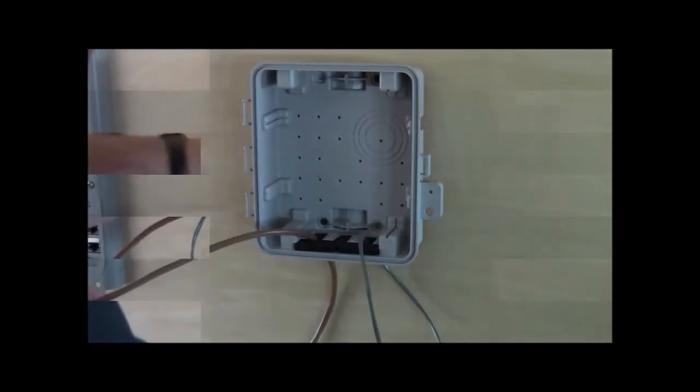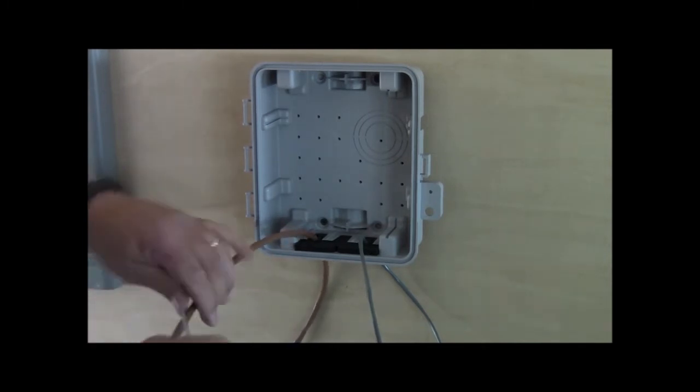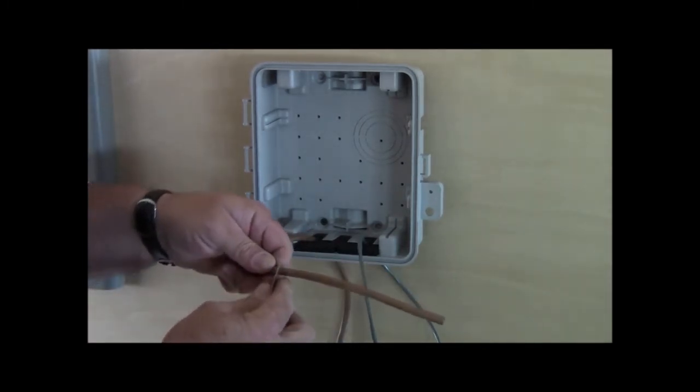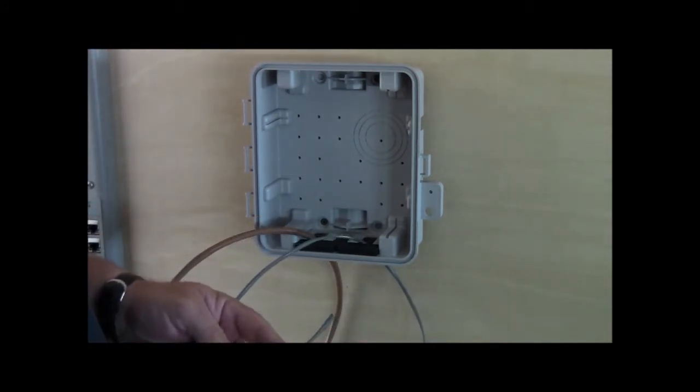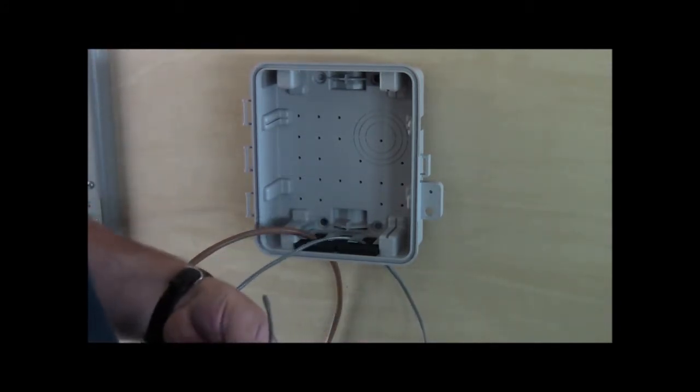Strip the outer insulation on the multi-conductor cable six to eight inches. There is not enough room on the round-jacketed cable between the battery and the enclosure. Strip the conductors in the multi-conductor cable three-eighths inches. Strip the two-conductor three-eighths inches.